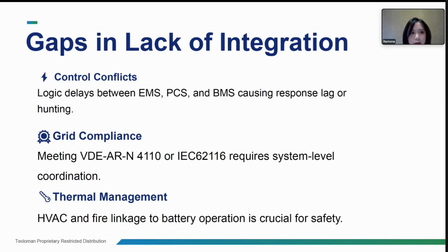Second, grid compliance. In Europe especially, grid requirements are becoming strict. Passing certifications on paper is not enough anymore, because the grid operator does not look at your batteries only. They look at the entire plant as one system, which means reactive power control, harmonic control, frequency response, and protection logic must all work together perfectly. Without system-level coordination, commissioning can become a nightmare. Sometimes projects can even be delayed for weeks.